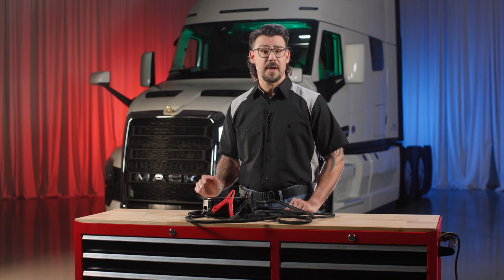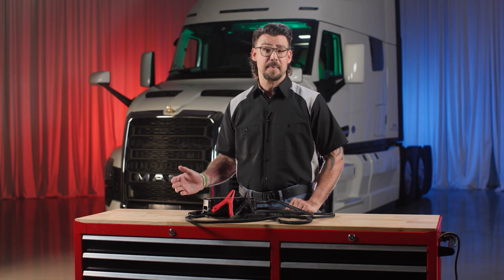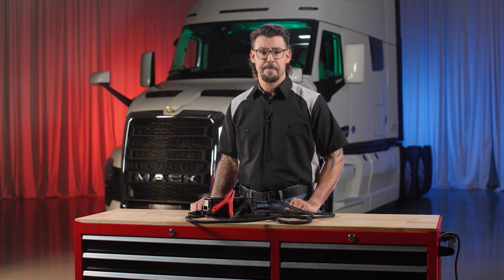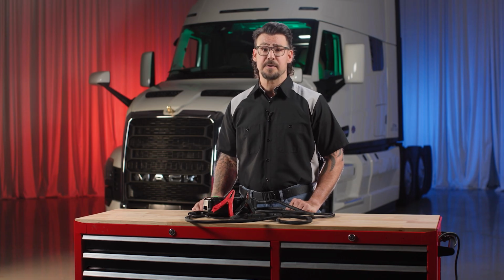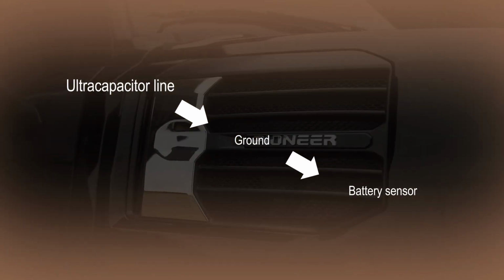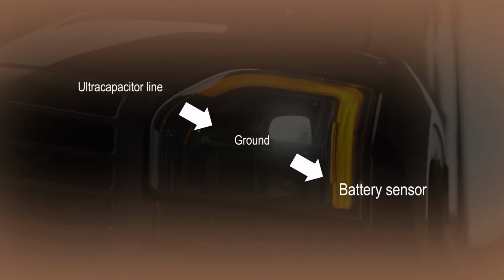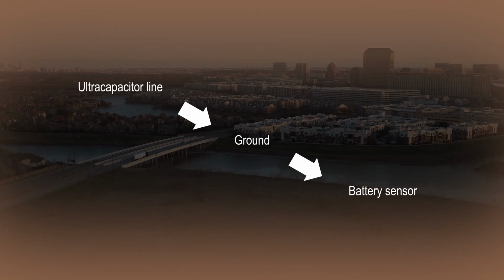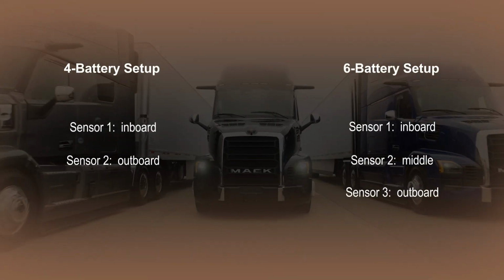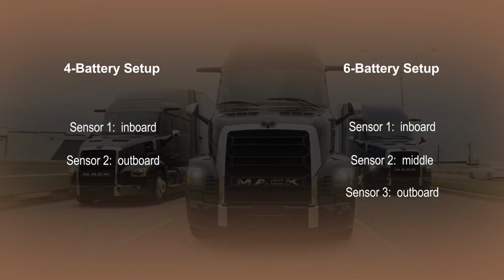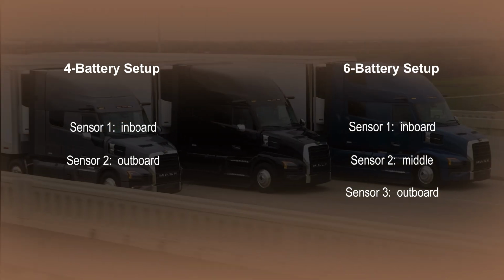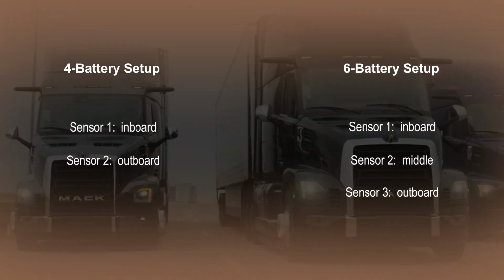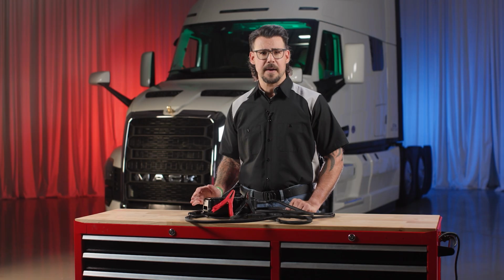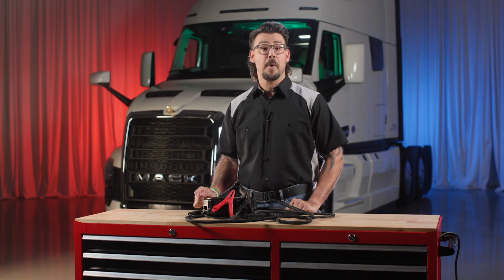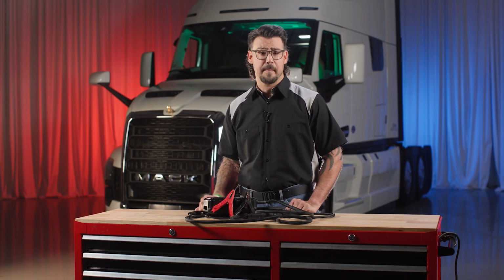Because the battery sensors are the foundation of the charging system, correct installation and service are essential. A single wrong connection or skipped calibration can throw off the entire system. When reconnecting, following the order of operations is very important. Start with the ultracapacitor line first, then ground, then battery sensors. It's important you do this before turning the maintenance disconnect switch back on. In a 4-battery setup, sensor 1 belongs inboard and sensor 2 outboard. In a 6-battery setup, sensor 1 is inboard, sensor 2 middle, and sensor 3 is outboard. Harness labels may fade or go missing, but just to be sure, use a multimeter on the harness code pin and confirm against the schematic.